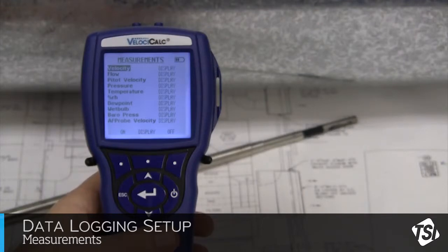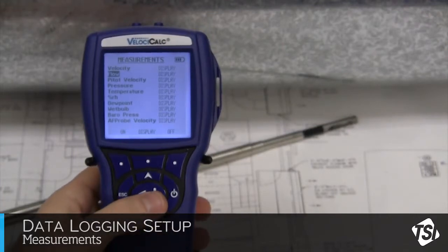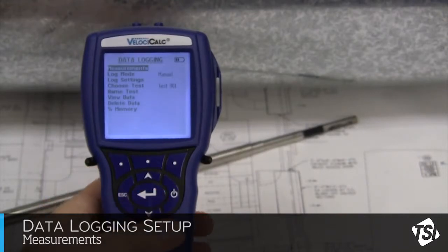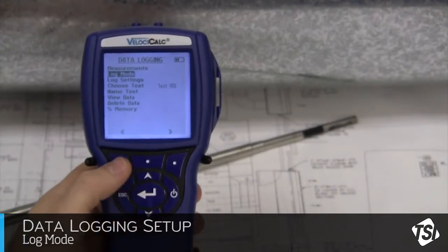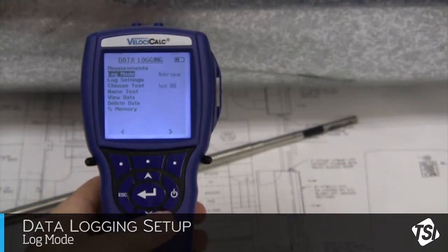Those measurements set to off will not be logged, and those set to on will be logged whether or not the measurement is displayed. You can use the soft keys to change these options. As long as Flow is set to Display or On, we can push the Enter button to save our changes and leave this screen. Now scroll down to Log Mode and use the left or right soft key to scroll through our options till Autosave is displayed. Using Autosave mode means we won't have to save each individual measurement manually. They will be saved automatically. This is the easiest logging method to use.